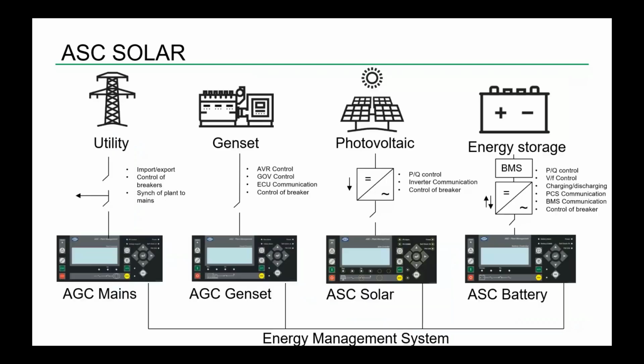So here's an overview picture of the energy management. Utility incomer on the left-hand side, that's the AGC mains. We have the plant control, set point control, import, export, of course, is a possibility. Also grid stabilizing features in the ADC mains, and synchronizing and breaker handling. The next controller is the genset controller, AVR control for voltage regulation, speed governor control. We have the full ECU communication and synchronizing and control of breaker, along with the other functionalities I mentioned.